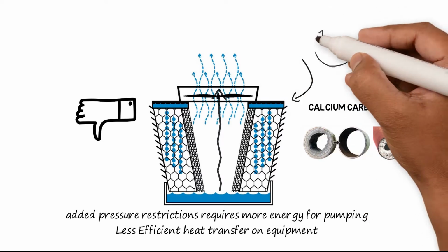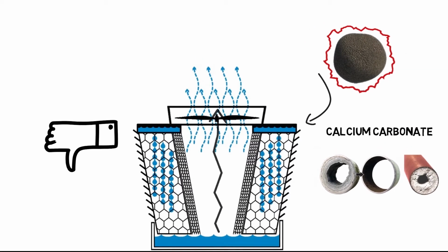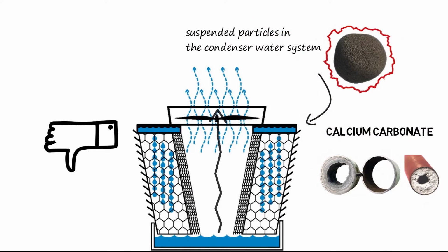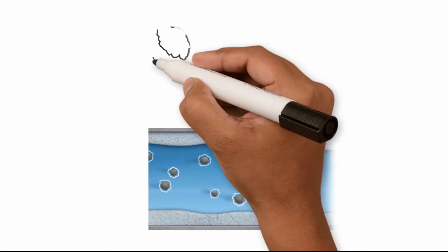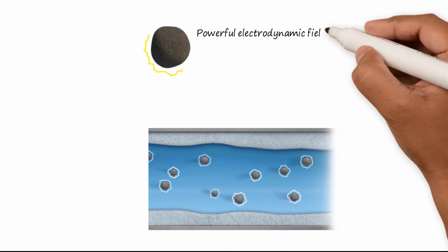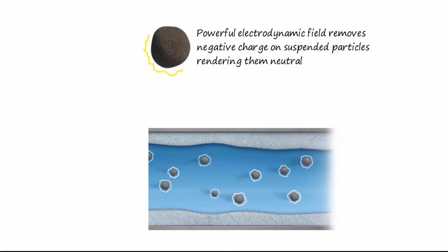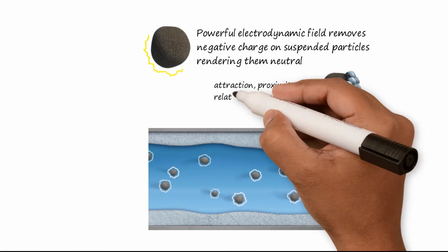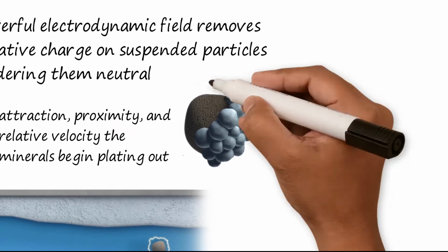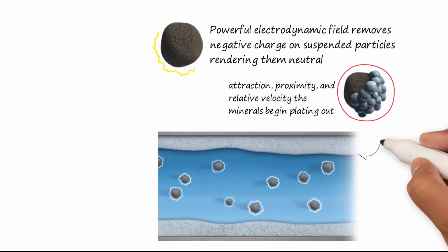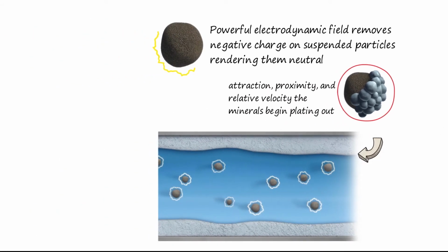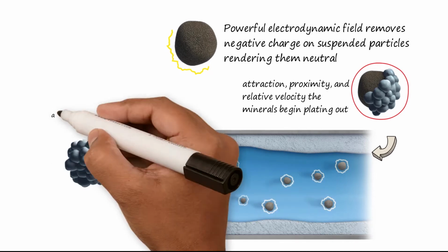Cooling towers act as a big air scrubber. The drawn-in dirt, dust, debris, and pollen become an infinite source of suspended particles in the condenser water system. When these suspended particles travel through the Wave's reaction chamber, the powerful electrodynamic field removes the negative charge from the suspended particles, rendering them electrically neutral. Then, the charge on the calcium carbonate minerals are now attracted to these neutral suspended particles. Due to this attraction, proximity, and relative velocity, the minerals begin plating out and forming on the surface of the suspended particles instead of forming on your equipment surfaces, thus preventing scale. Soon, the formations become a harmless powder where they are flushed out as part of your normal cooling tower operation and routine service.